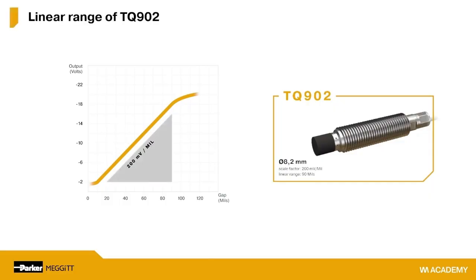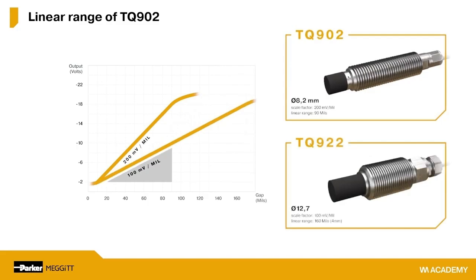To give you an example, while we have depicted the scale factor and linear range for a typical probe system with an 8 millimeter diameter tip, like our TQ902, the scale factor and range for a probe system with a 13 millimeter diameter tip, such as our TQ922, will be different. In the case of the TQ922, the scale factor can be ordered as 100 millivolts per mil, and the linear range will be twice as large at 160 mils. Other probe systems with even larger tip diameters will give even larger linear ranges, but correspondingly smaller scale factors. Such probes are used in applications such as differential expansion, where gaps greater than 4 millimeters or 160 mils are required.